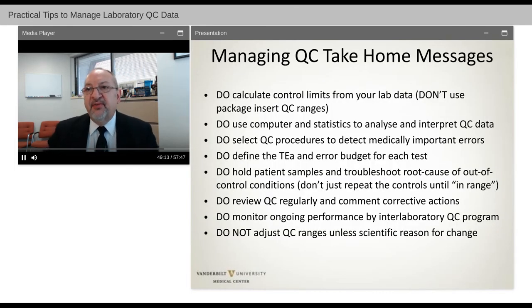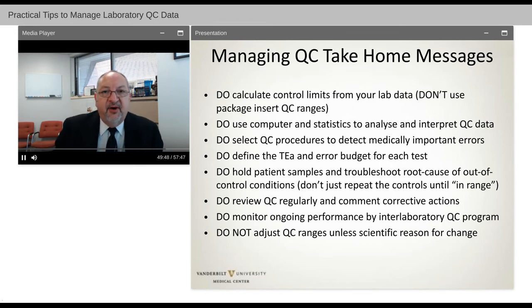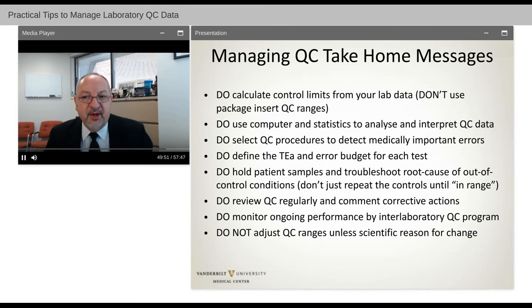I'm going to close by wrapping up with some QC take-home messages. Do calculate your own quality control limits from your lab data. Don't necessarily utilize what's in the package insert. Use computer and statistics to analyze and interpret quality control data, and select QC procedures to detect medically important errors. Define your total allowable error and your error budget for each test. Hold patient samples when controls go out of range. Troubleshoot the root cause of out of control conditions and fix those problems.